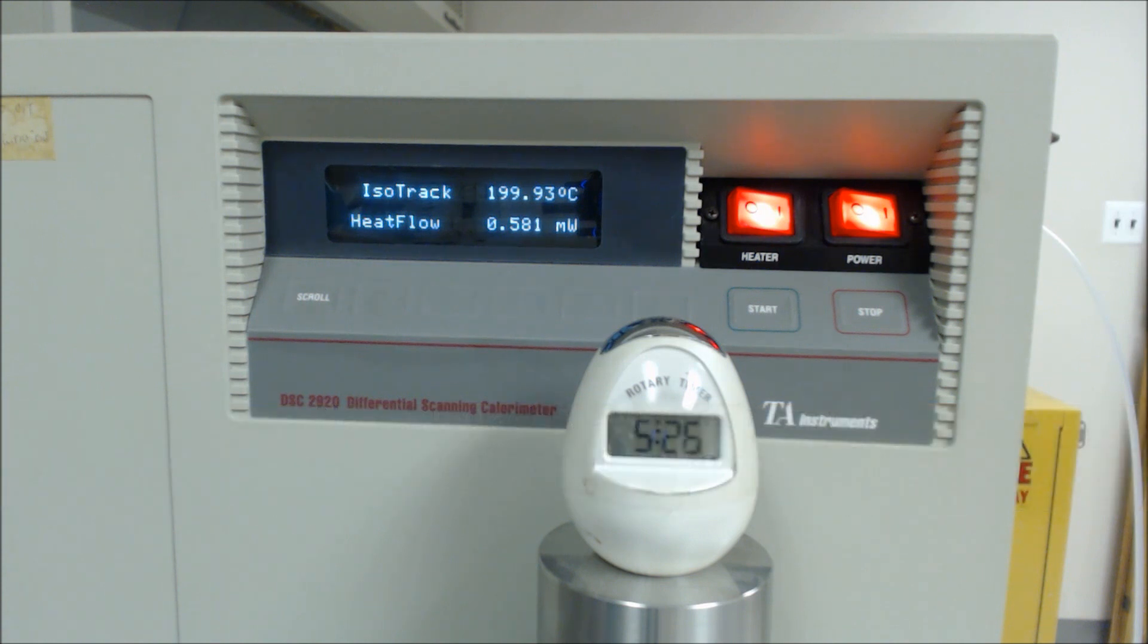After the T sub 0 is passed, the cell continues its isothermal track at 200 degrees C. This is by far the longest portion of the test. At this point, there is nothing to do but wait for the oxidative onset to occur. For standard OIT, GSI sets the second iso track to run for a duration of 300 minutes, as 5 hours is plenty of time to experience the oxidative onset and subsequent exotherm for most HDPE geomembranes.